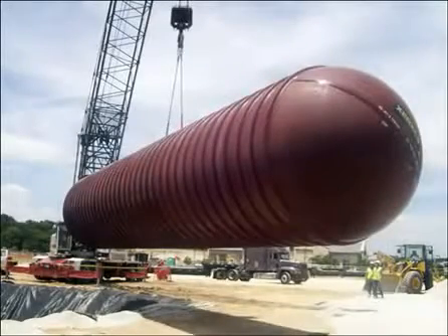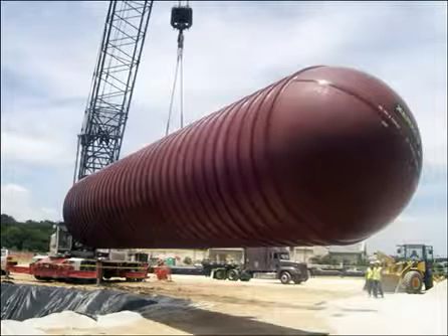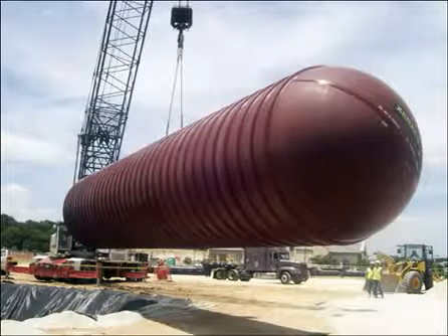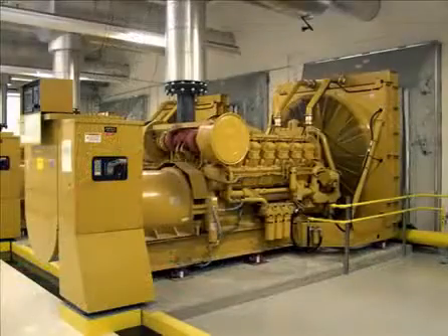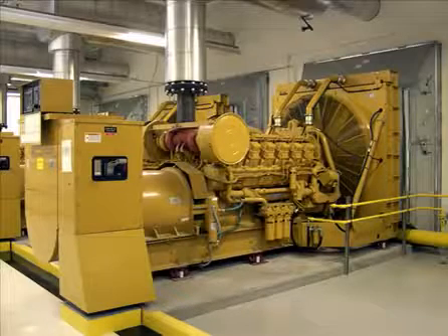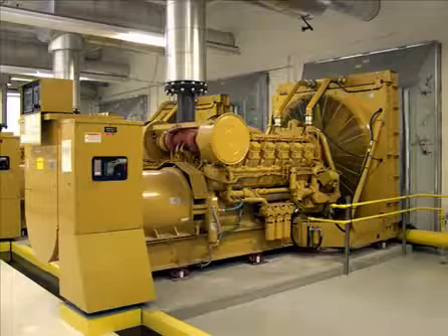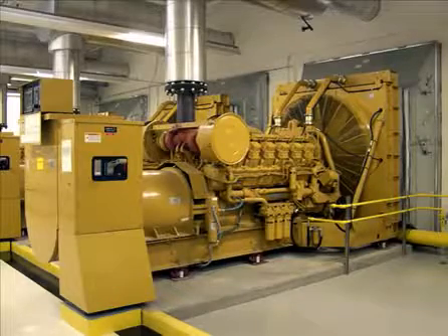The first step in determining the fuel volumes is to know the duration of emergency power required. This is set either by the Life Safety Code, a state regulation of facilities such as hospitals, or a management decision for operational security. Typical design durations are 8, 24, 48, 72, or 168-hour, 1-week durations.